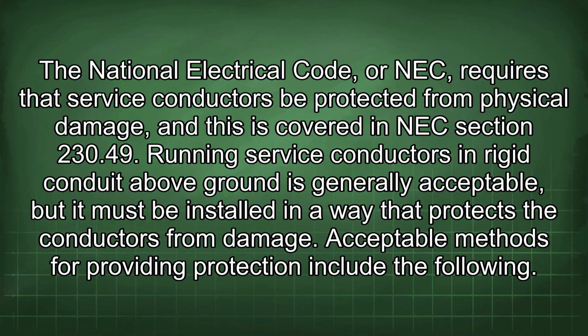The National Electrical Code, or NEC, requires that service conductors be protected from physical damage, and this is covered in NEC section 230.49. Running service conductors in rigid conduit above ground is generally acceptable, but it must be installed in a way that protects the conductors from damage. Acceptable methods for providing protection include the following.